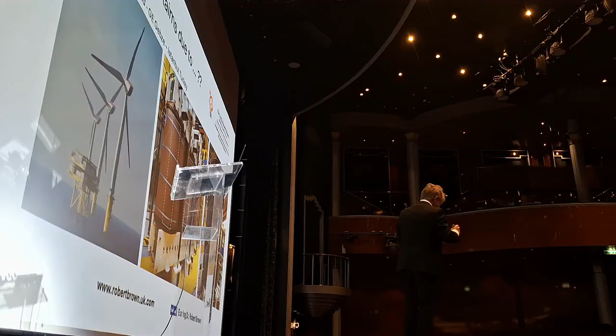So what happened in this case is, in the offshore substation, the temperature of the oil is monitored. And also, if you've got a frying pan at home, or oil in a pot, if you start to heat it, you see it generates bubbles. That's the minerals in the water reacting with the heat, and it's generating a gas. So they also monitor the gas.